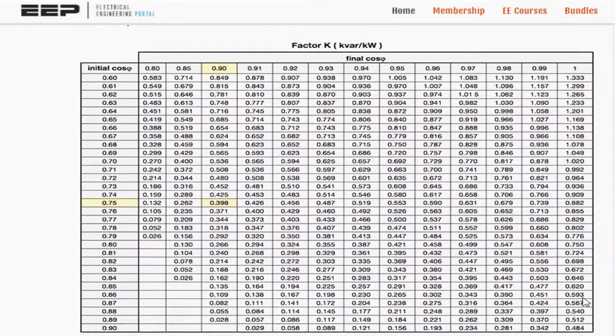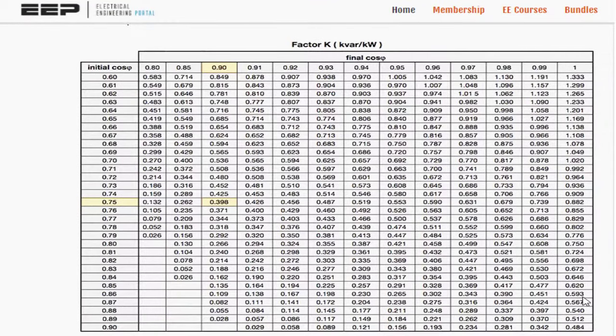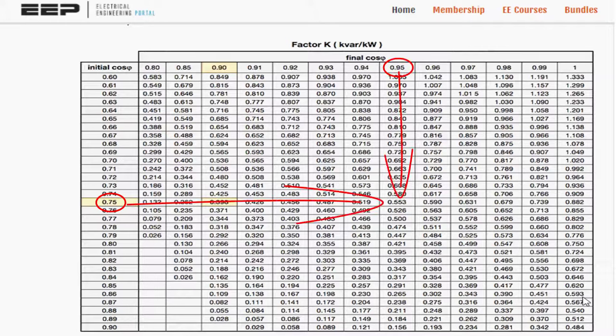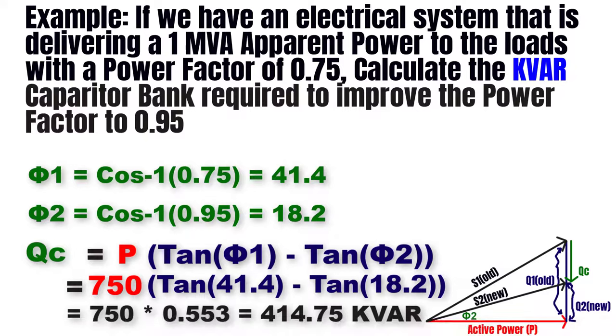We can also use a table to find tan phi1 minus tan phi2 directly without calculations. With an initial power factor of 0.75 improved to a final power factor of 0.95, they meet at the value 0.553. So Qc equals the power times 0.553, which equals 414.75 kVAR — the same result as before. You can find the link to the table in the description. Stay tuned to our ultimate industrial classic control course on YouTube.